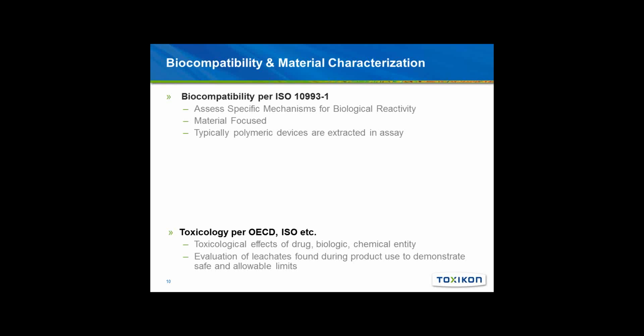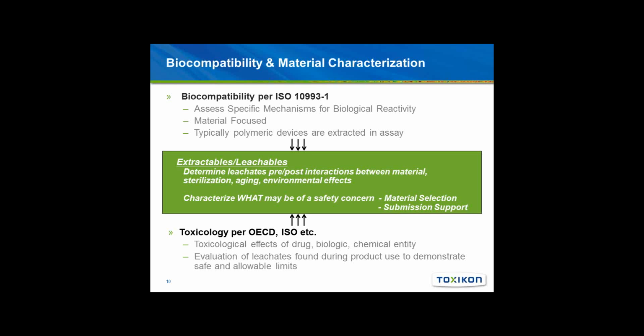If you look at the toxicology of different compounds, different additives, that's where we are looking at the type of effect a chemical compound has. So there we're evaluating the leachates that are found during product use, the device in contact with the patient clinically, and we want to demonstrate safe and allowable limits of these compounds that are delivered to the patient. And how we can model that is with extractable and leachable testing. That's the chemical characterization, material characterization. Here we can determine the leachates, pre and post interactions between material, sterilization, aging, environmental effects, everything that we've talked about that affects extractability, and how we can characterize what may be of a safety concern.